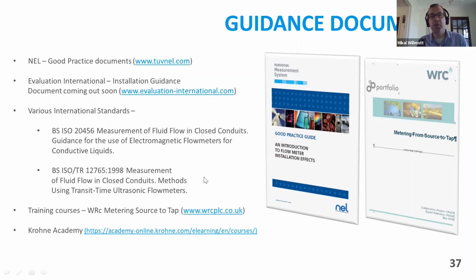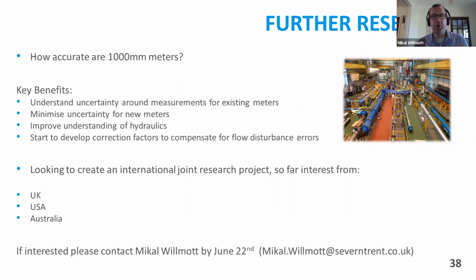We're still looking to do further research. As you see from today, we've learned a lot over the last 10 years. There's still lots of things that we need to understand. And we really want to look at large meters, so 1,000 mil meters. As we say, these meters are disproportionately important to the water balance. I know one UK company, about half their system import volume goes through about 8 or 9, maybe even less than that, 1,000 mil meters or bigger. So really, really important. As we know, there's a difference between 250 mil and 500 mil performance-wise, we want to know there's a difference between 500 mil and 1,000 mil. That's important for uncertainty. That's important for installation guidance.